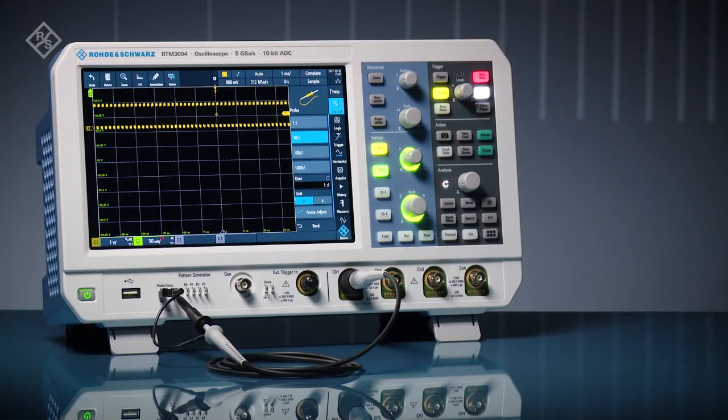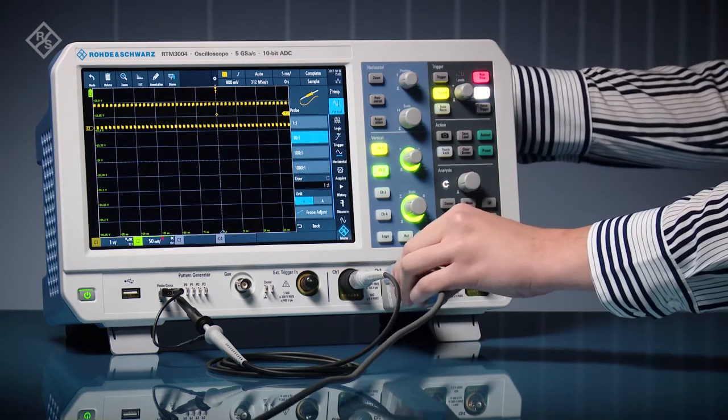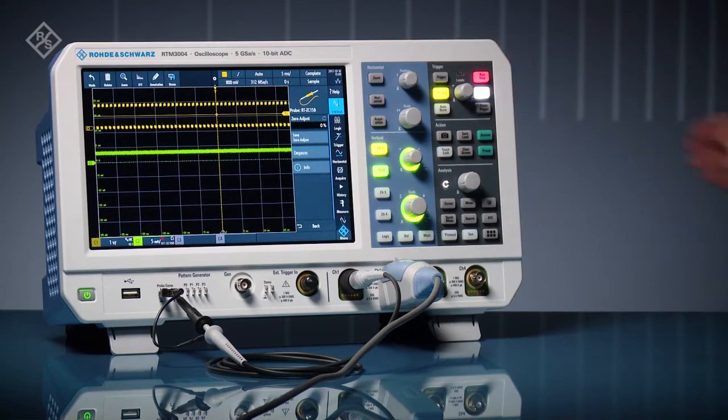Rohde & Schwarz RTM 3000 and RTA 4000 Series Oscilloscopes include the Rohde & Schwarz probe interface. The interface supports passive probes and auto-detects attenuation ratio. Choose from one of the many available current probes. The oscilloscope automatically detects the probe and sets up the scope, like showing vertical scaling in amps.